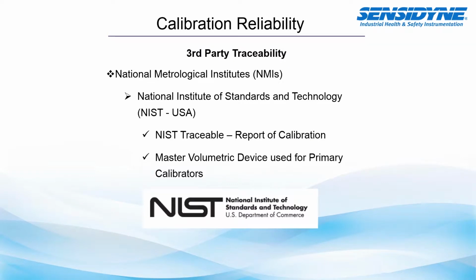So third-party traceability relates to an agency ability to standardize units of measurement. So worldwide, there are national metrological institutes. In the United States, we use NIST, which is the National Institute of Standards and Technology. It's a division of the U.S. Department of Commerce. When we see things that are NIST traceable, which you'll want to see on your calibration reports, it means that it is brought up to this higher standard that can really be compared. Also, they use a master volumetric device for primary calibrators. And we'll talk a little bit about what separates a primary calibrator from a secondary calibrator as we move forward in this presentation.